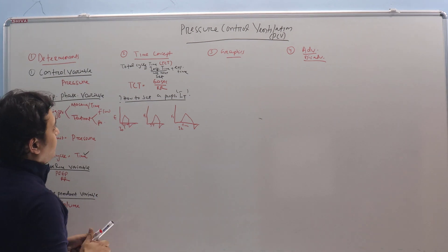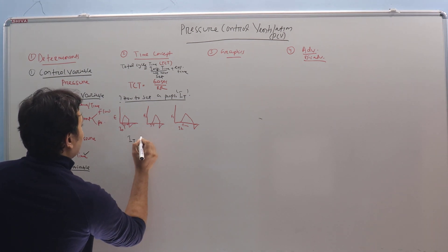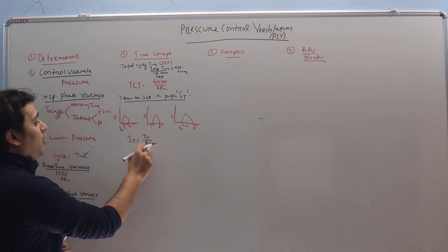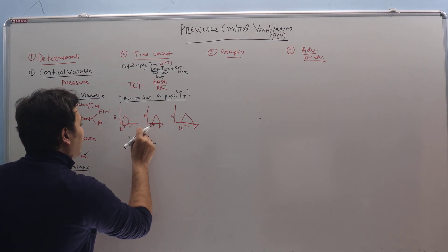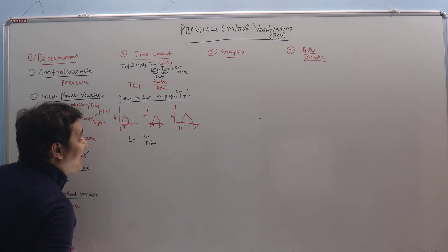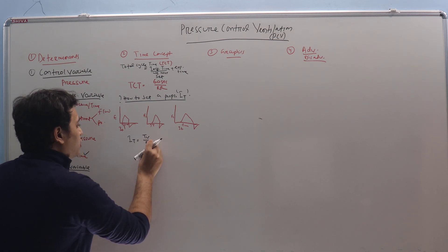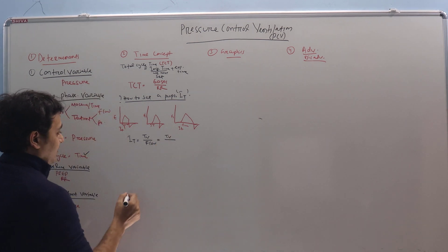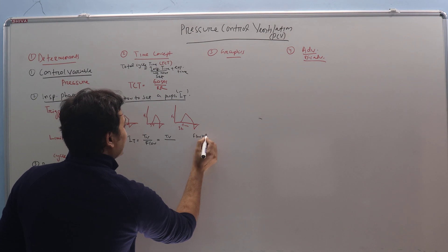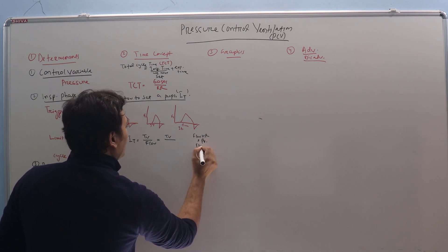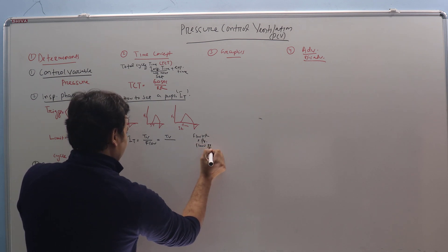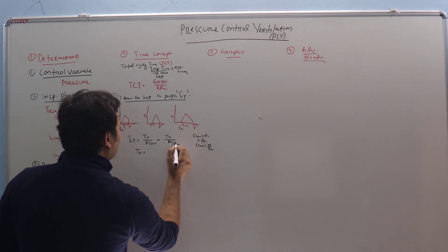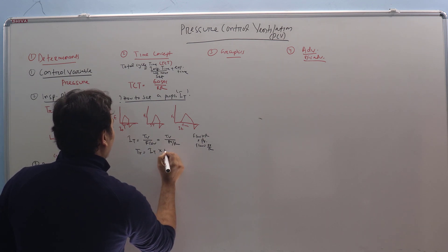Using another formula: Inspiratory Time equals tidal volume divided by flow. In pressure control ventilation, we are setting the Inspiratory Time, not the tidal volume or the flow — so those will be variable. That is one of the advantages. Since we know that flow times resistance equals pressure, flow equals pressure divided by resistance. Replacing flow, tidal volume equals Inspiratory Time times pressure divided by resistance, so with resistance constant, tidal volume is proportional to Inspiratory Time and pressure.